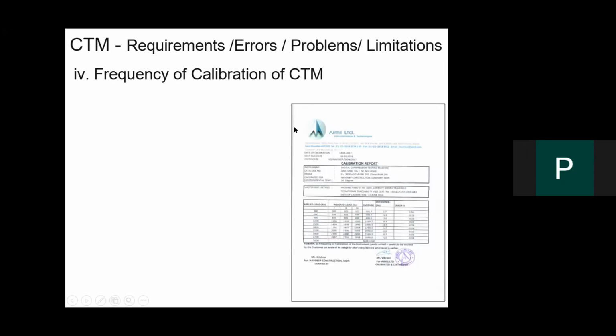Sometimes I have to put a 'whitener' on that area, but unfortunately, even in different agencies, they say, Mr. Raje, we will give the calibration certificate. My next question is related to this: you are giving me the calibration certificate, but you have to give me your detailed proving ring certificate. Whether the proving ring used to calibrate my machine is valid or not. If it is not valid, then why should I take calibration, and why should I pay you?